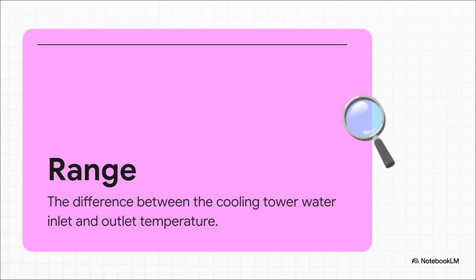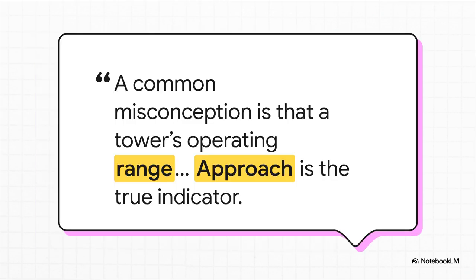Range is super simple. It's just the temperature drop, the difference between the hot water going in and the cold water coming out. But here's the kicker: the tower itself doesn't decide its own range. The power plant does. The plant sets the heat load, and the tower's job is just to handle whatever's thrown at it.